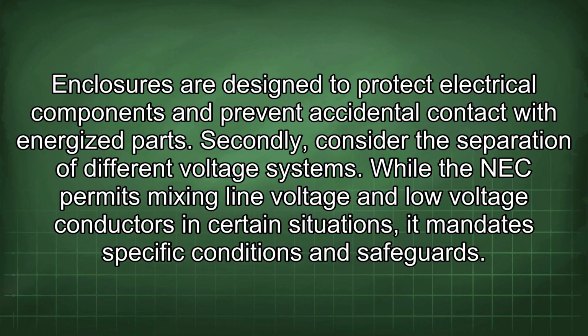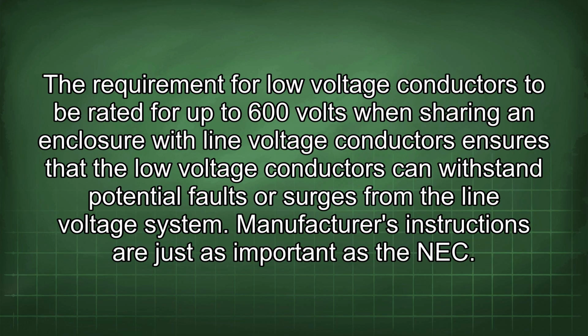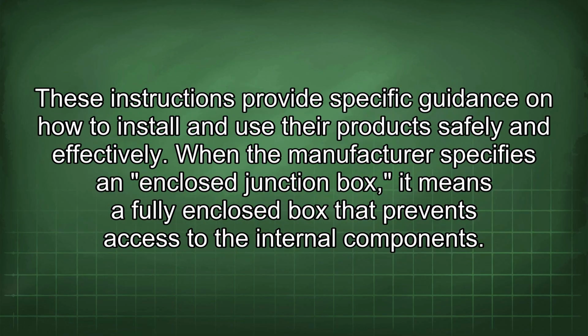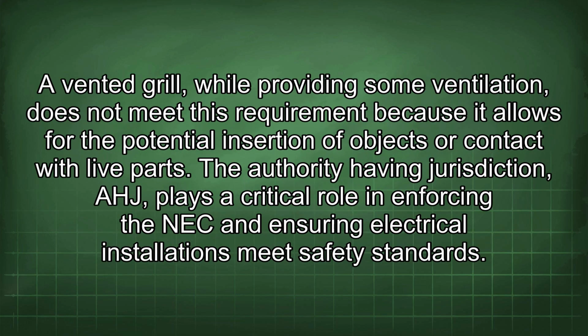Secondly, consider the separation of different voltage systems. While the NEC permits mixing line voltage and low voltage conductors in certain situations, it mandates specific conditions and safeguards. The requirement for low voltage conductors to be rated for up to 600 volts when sharing an enclosure with line voltage conductors ensures that the low voltage conductors can withstand potential faults or surges from the line voltage system. Manufacturer's instructions are just as important as the NEC. These instructions provide specific guidance on how to install and use their products safely and effectively. When the manufacturer specifies an enclosed junction box, it means a fully enclosed box that prevents access to the internal component. A vented grill, while providing some ventilation, does not meet this requirement because it allows for the potential insertion of objects or contact with live parts.